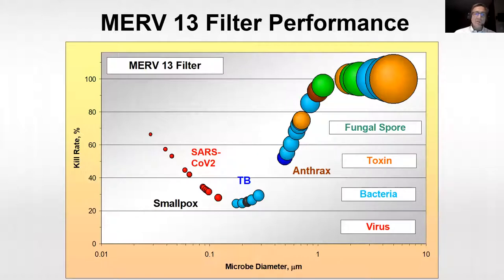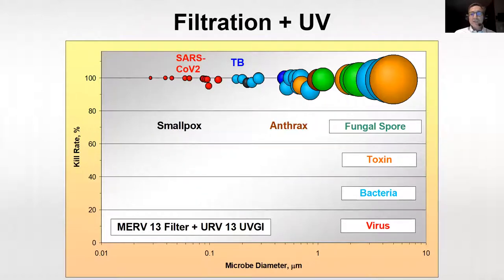Now, the idea with UV is not to replace the filter, but to complement the filter. If we add UV on top, here's what we can get by adding UV after filtration. We can totally eliminate, and I'll explain how it works, the TB, for instance, and SARS-CoV-2, without increasing the pressure drop. That's the nice part about it. So you don't impair the flow and you don't increase the pressure drop, and you can get performance as good as a HEPA filter without the inconvenience.